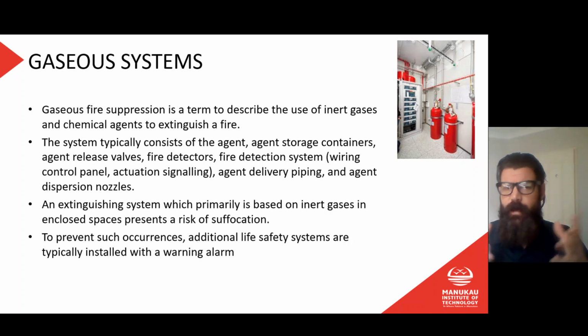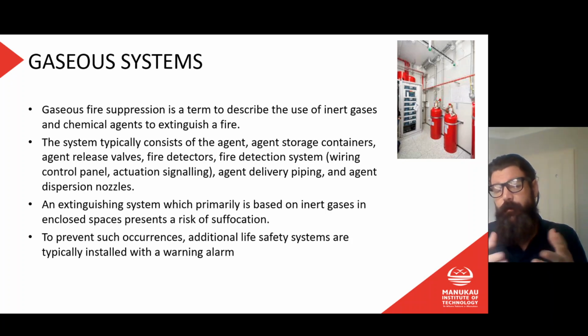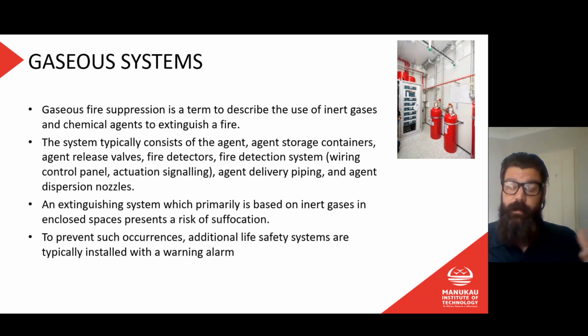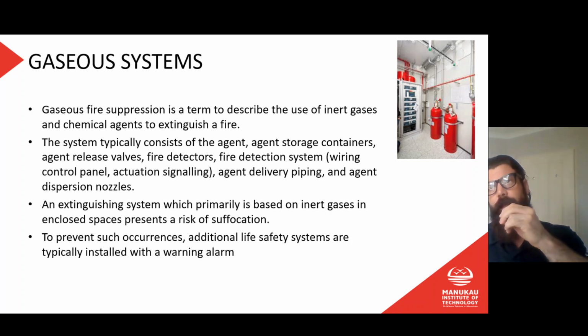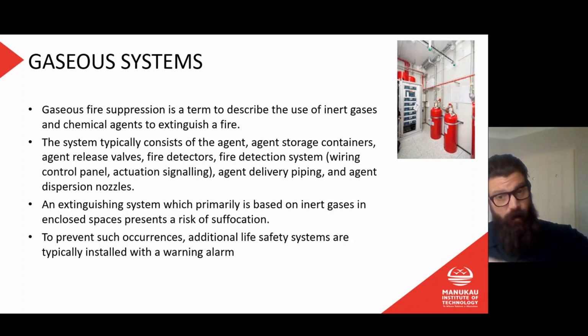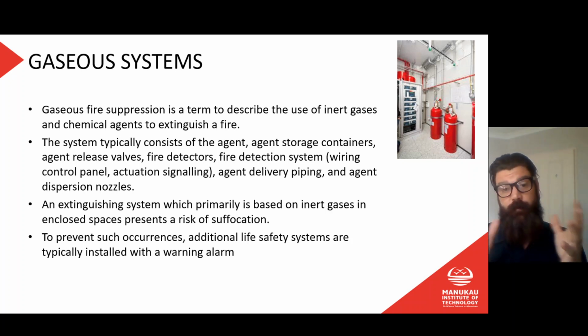Now that works, it's similar to the CO2 fire extinguisher in that it's depriving the fire of oxygen, but it doesn't work in the same way as a CO2 extinguisher. As I said, the extinguisher is going to spray CO2 straight onto the fire, and thereby, as it moves over the fire, displacing the oxygen. In a CO2 or gas fire system, it's going to fill the room with that gas, and then obviously there's no more oxygen left, so the fire will go out.